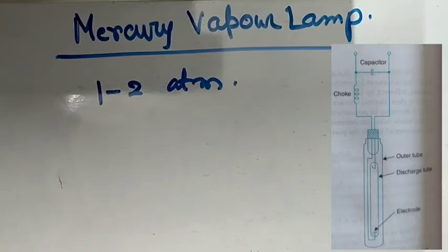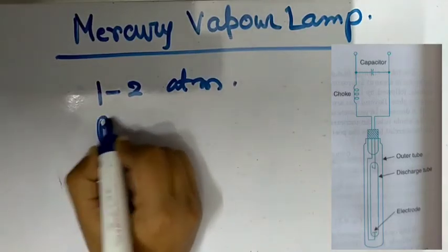When the mercury vapor lamp is in use and goes out, it will not restart until it has cooled down and the vapor pressure has fallen to a value sufficiently low to allow restriking of the discharge in the inert gas. The overall efficacy of the bulb is approximately 35 lumens per watt, and the power factor is 0.65.